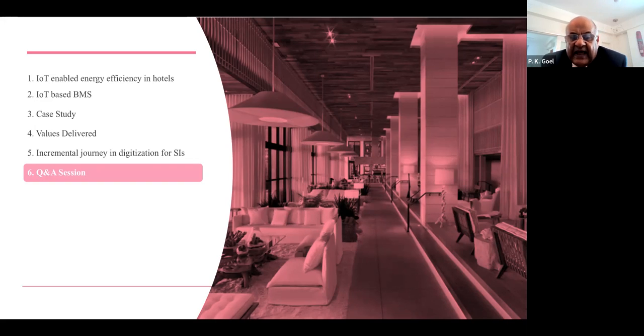In fact, I'll mention that as much as it's beneficial after so many years, it's always beneficial when you start the project too. Because at the end of the day, project execution is translation of design onto the ground. Calculation of pump heads is not a difficult thing, but it's something that doesn't get done very much upfront in the industry. So you get situations where the pump head calculated was much more than what actually exists, so you're operating at a much lower head with a much larger flow rate, and spending far too much energy on your pump than required.